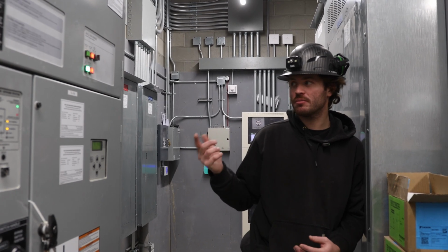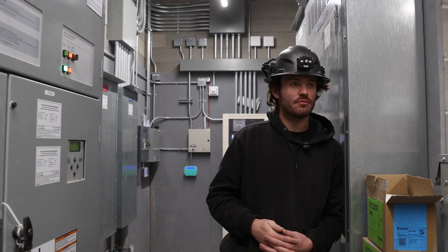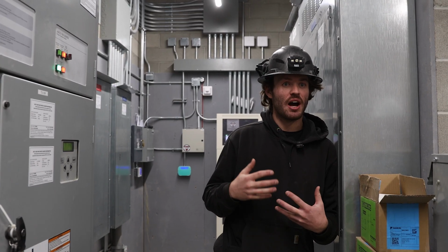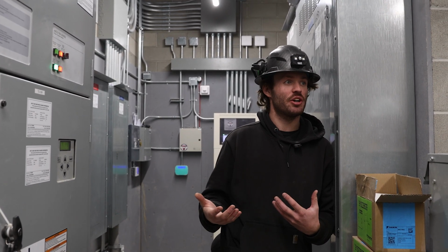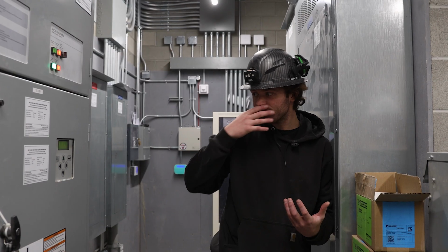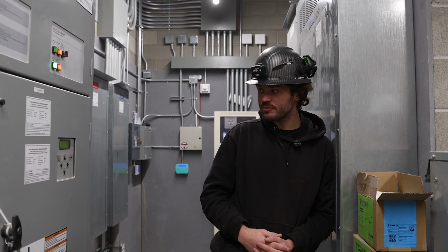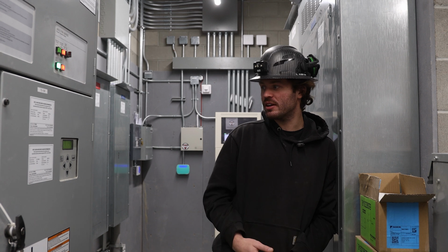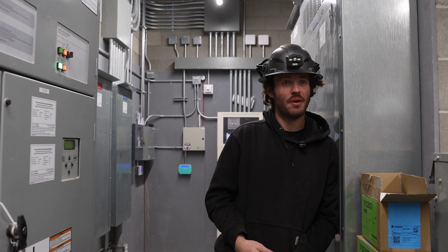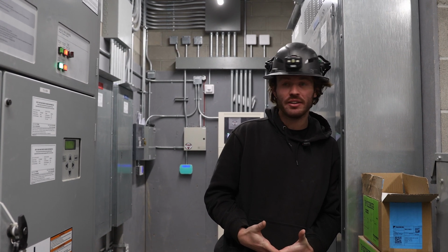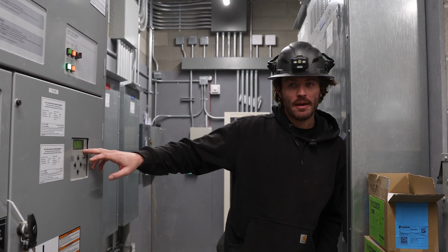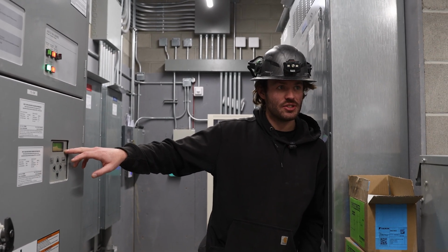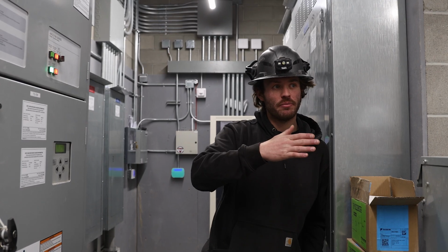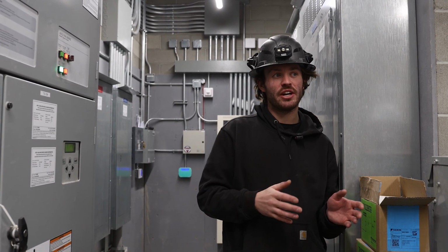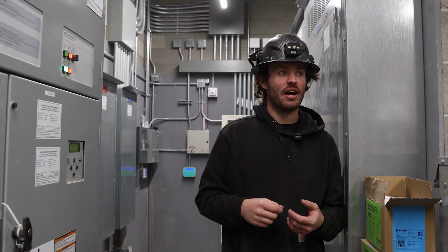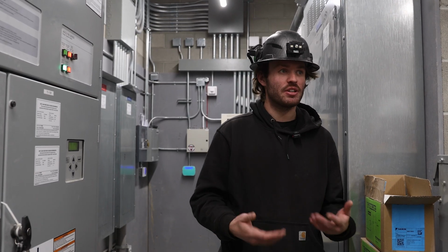So it's about to transfer. There's power transfer. Very seamless. I've even had computers not shut off when doing transfers like that. Our post-transfer timer is going back to the elevator, letting it know to do something. I don't exactly know what it's telling the elevator. And now we'll start an hour timer. This hour timer is how long the generator needs to run for. At this point, you go back out to the generator with your logbook, start recording values, start watching it, making sure all is good.